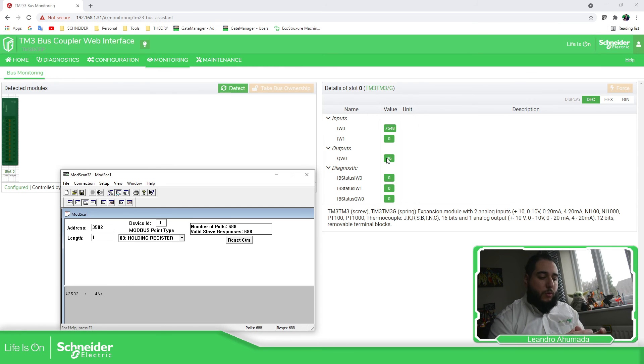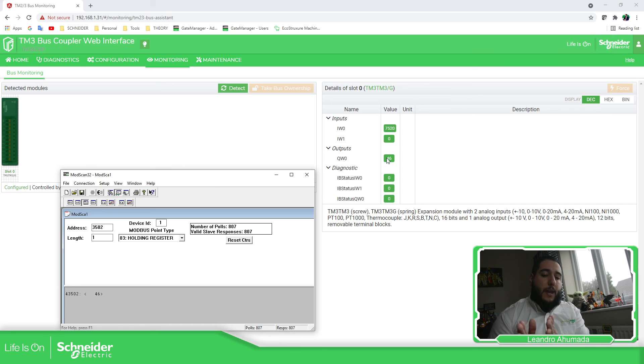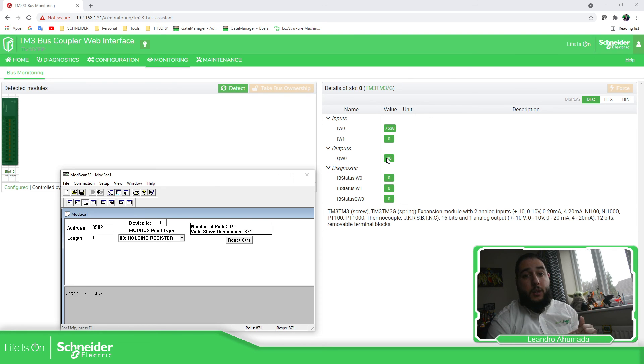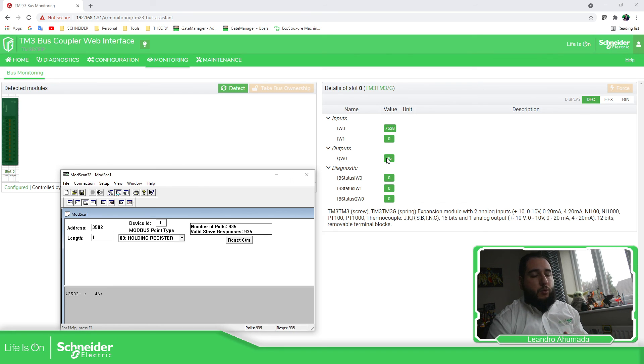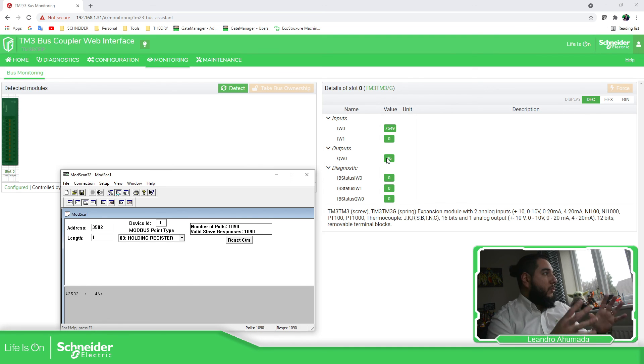The bus coupler will allow you to have a remote I/O island. You can add all the TM3 modules you want, up to seven. If you want more, you will need to add a transmitter and receiver. Once the configuration is downloaded into the bus coupler, you should be able to access the Modbus holding registers on the bus coupler. Then using third-party software or a PLC, you should be able to read information. One advantage of using the Modicon M221 or a Modicon PLC in EcoStruxure Machine Expert is that the configuration is handled in the software and downloaded to the bus coupler automatically, so you don't need to go through these manual steps.